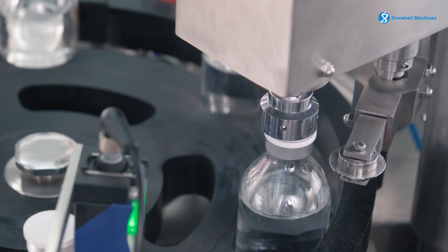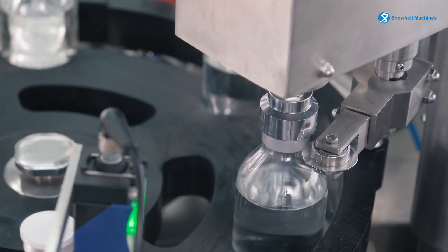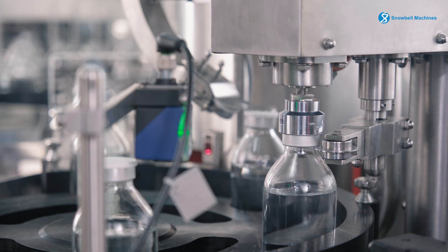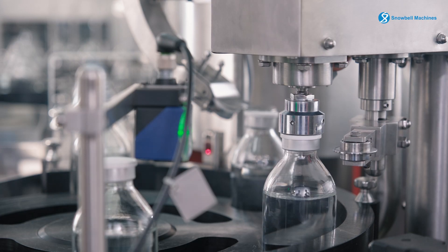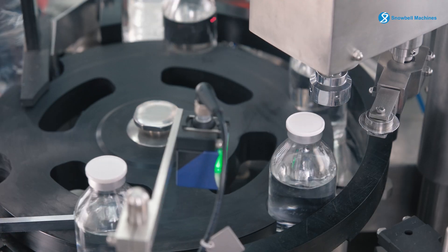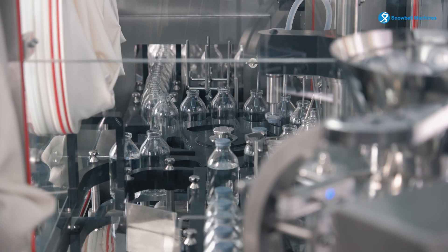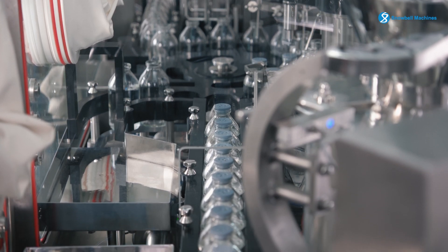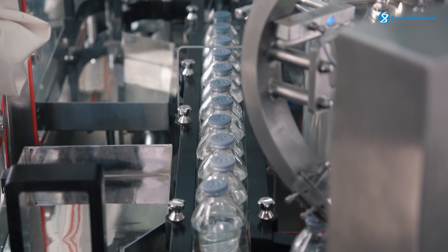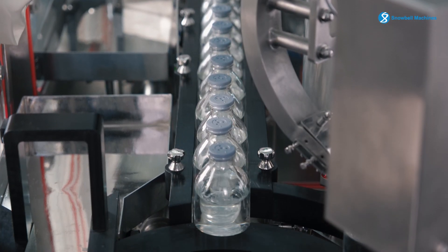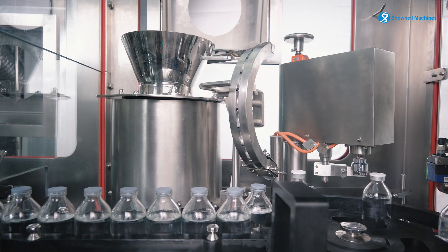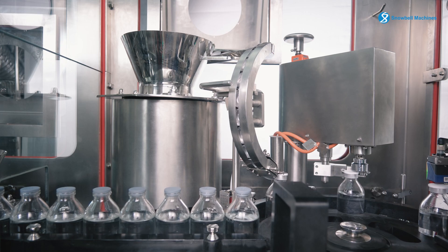The cap sealing machine seals the vials and bottles with pre-sterilized caps. Caps are fed into the isolator through a rapid transfer port.